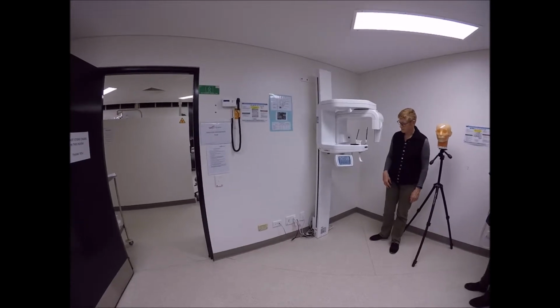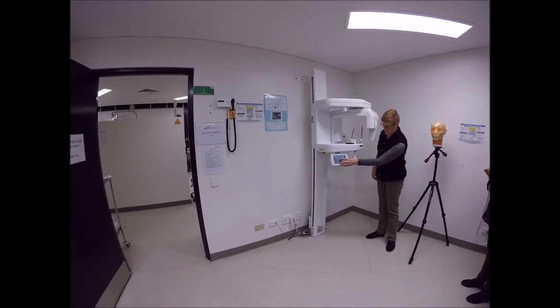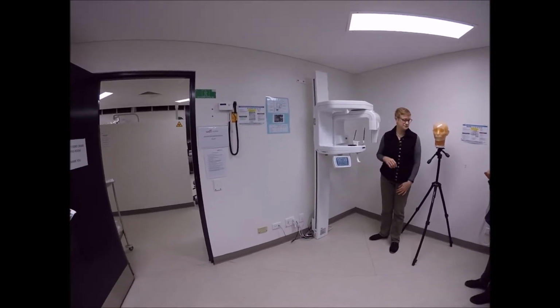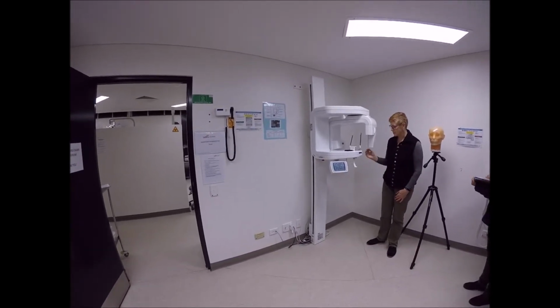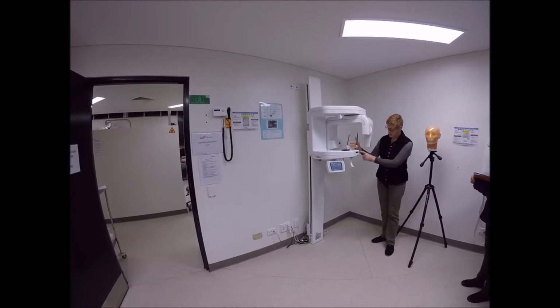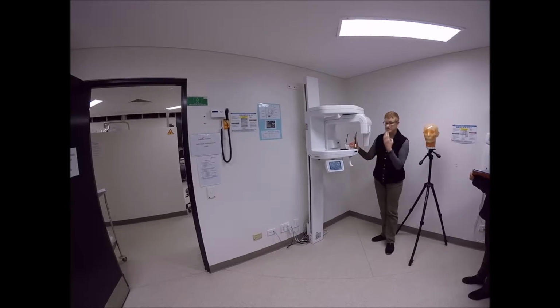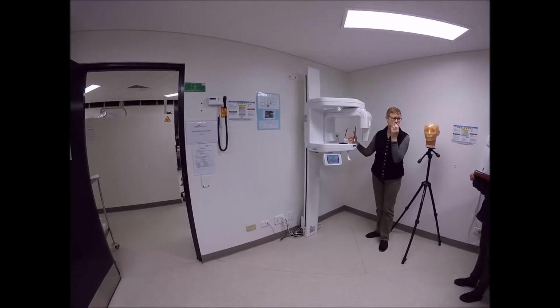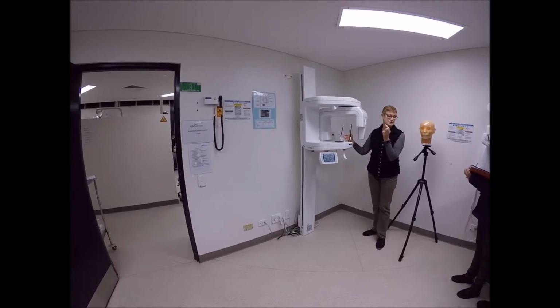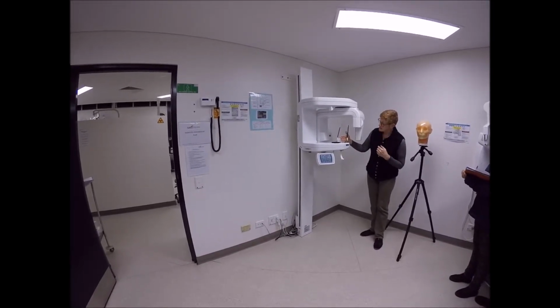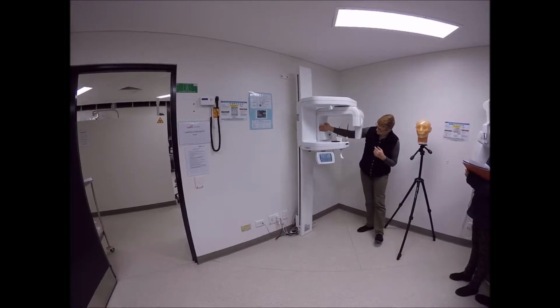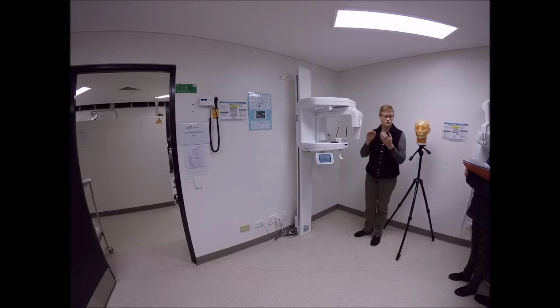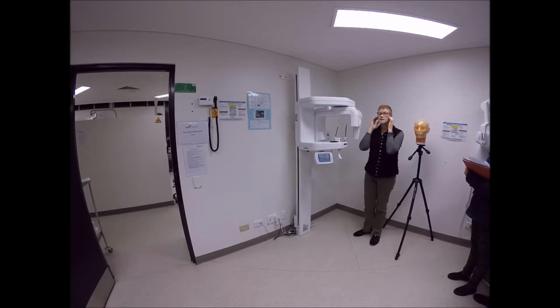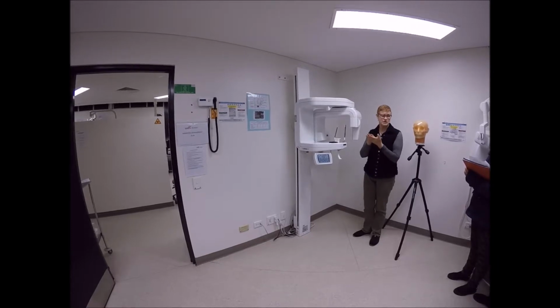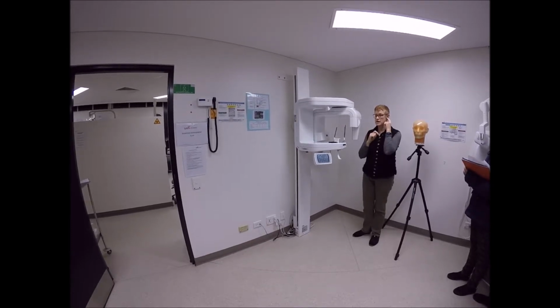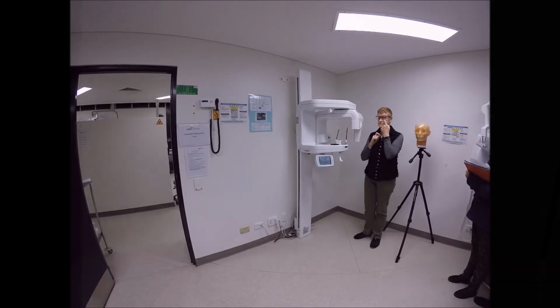You might have noticed as I hit the layer arrows that some lights came on. We have 3 light beams. We have one that's projecting from the side here, and that helps us line up the anterior segment of the arches in the focal trough anteriorly. There's a horizontal line that allows us to get the head posture correct, the up-down tilt of the head, and that line we try to get it parallel to Frankfurt horizontal, which is tragus of the ear to the lower rim of the orbit.